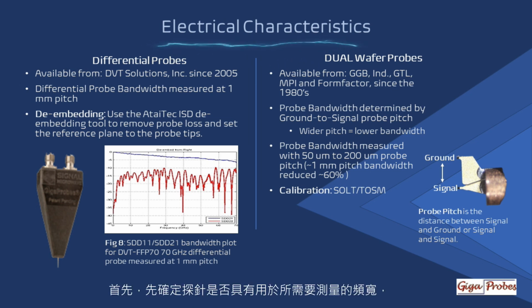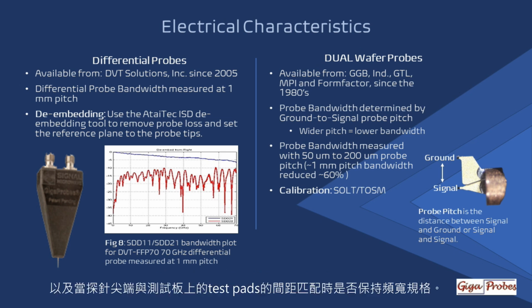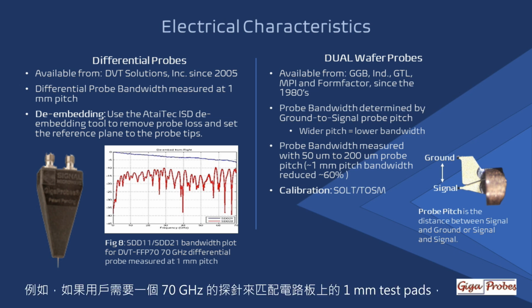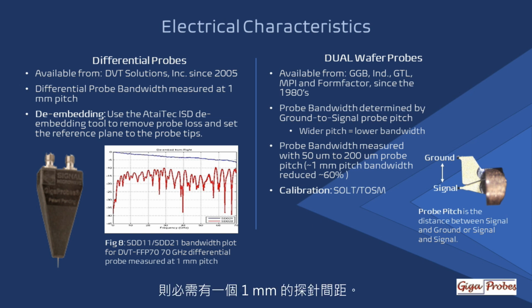First, determine if the probe has enough bandwidth for your measurement and whether the bandwidth specification is maintained when the probe tips match the spacing of the test pads on your board. For example, if you need a 70 GHz probe to match the 1 mm test pads on your board, you must have a 1 mm probe pitch.